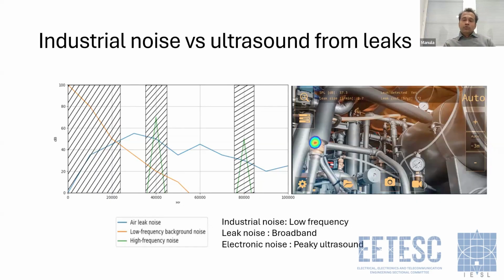There, the background noise is at 80 to 90 decibels. In this graph, the x-axis is the frequency and the y-axis is the sound pressure level in decibels. The orange graph shows the background noise, while the blue graph shows the air leak noise. The background noise dominates in the low frequency range, in other words the audible range. That's why we hear a lot of audible noise in these environments. But at ultrasound levels, gas leaks dominate over the industrial noise.